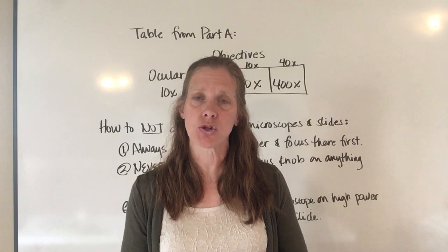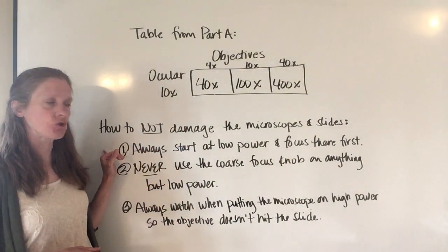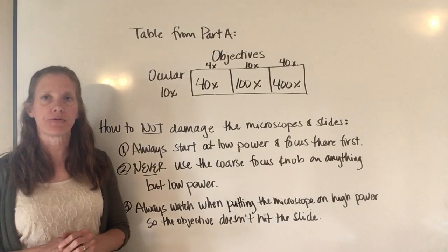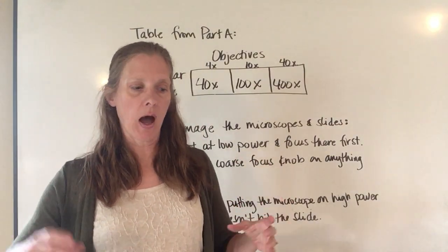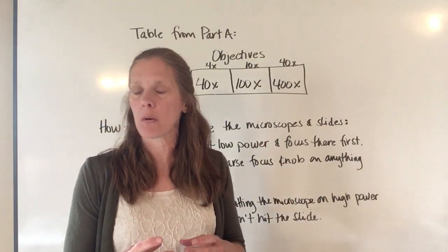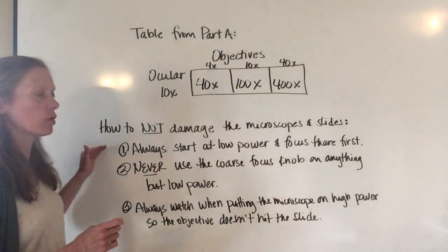There are three safety rules I want to emphasize as you're using a microscope so we don't damage anything. First, always start at low power and focus there first. Eventually we want to get to high power, but the higher power you go, your field of view shrinks every time. You have to start at low power, get it focused there, then go to increasingly higher power.